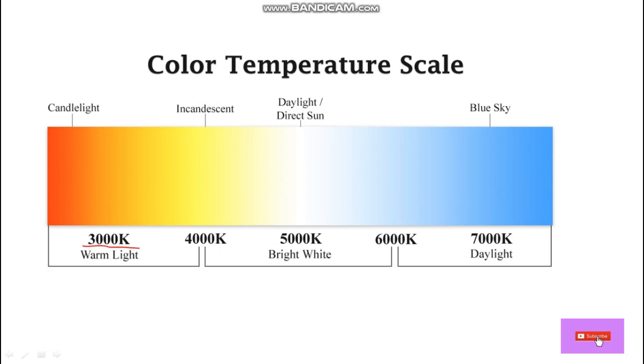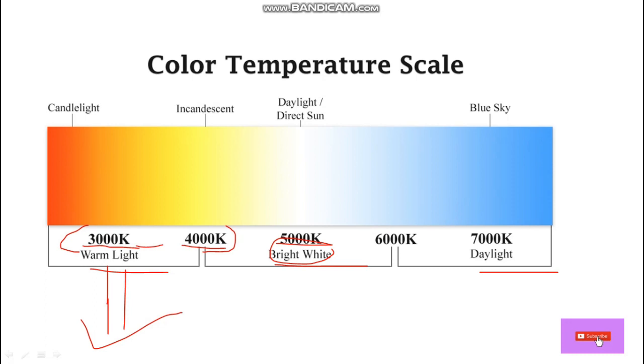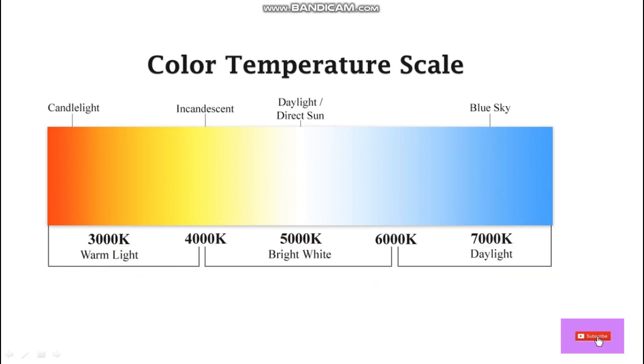Color temperature gives the color of the light according to its value. We have three ranges: warm light at 3,000 to 4,000 K, bright white light at around 5,000 K, and daylight or cool light at 7,000 K. These are the parameters for light color that we need to know before selecting or purchasing a light fixture.